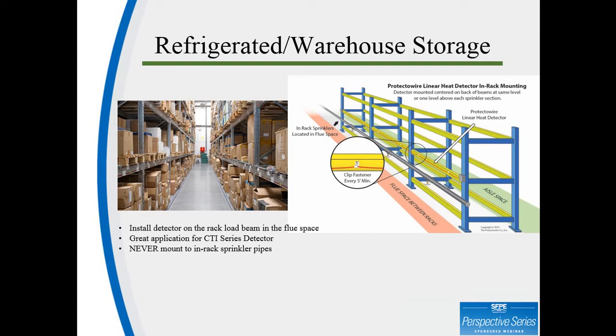This is why I'm emphasizing two things in this slide. If you want to use standard linear heat detection, do not put it on the pipes, put it on the back of the load beam. And the second is that you should use the CTI series to assure that you do not flow any water until there is actually heat present. Finally, if you're unsure where to put the linear detector, FM datasheet 8-29 suggests one run of linear detection for each row of in-rack sprinklers.